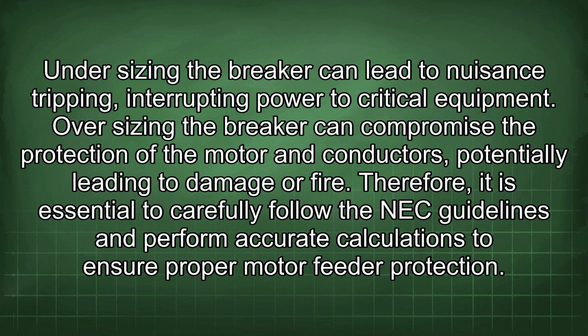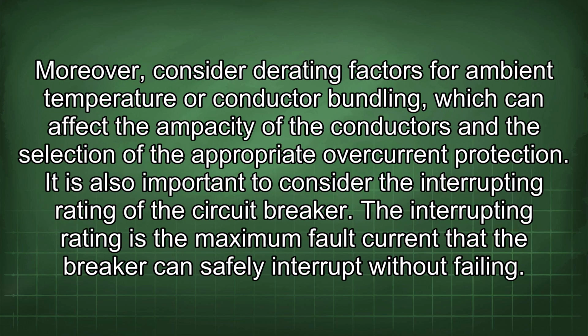Undersizing the breaker can lead to nuisance tripping, interrupting power to critical equipment. Oversizing the breaker can compromise the protection of the motor and conductors, potentially leading to damage or fire. Therefore, it is essential to carefully follow the NEC guidelines and perform accurate calculations to ensure proper motor feeder protection. Moreover, consider derating factors for ambient temperature or conductor bundling, which can affect the ampacity of the conductors and the selection of the appropriate overcurrent protection.